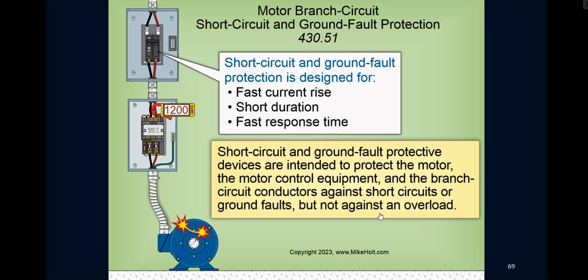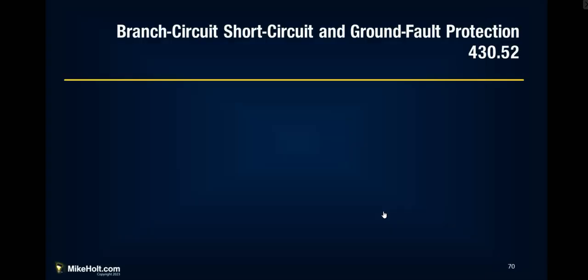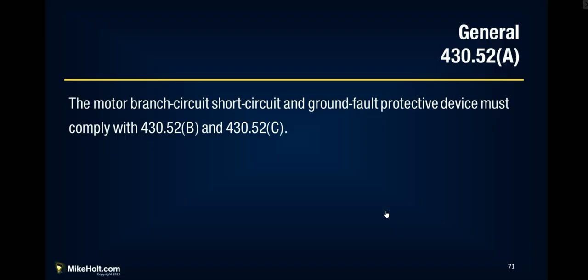So short circuit and ground fault protection is designed for fast current rise, short duration, fast response time. Everybody in this meeting by now has tripped a breaker, and that's exactly what it's for. Short circuit and ground fault protective devices are intended to protect the motor, motor control equipment, and the branch circuit conductors against short circuits or ground faults, but not against overloads. The motor branch short circuit and ground fault protective device must comply with 430.52B and C. And if you got your code book, we're going to jump over a little bit here. Go to 52, which table 430.52C1, maximum rating or setting of motor branch circuit, short circuit, and ground fault protective devices.